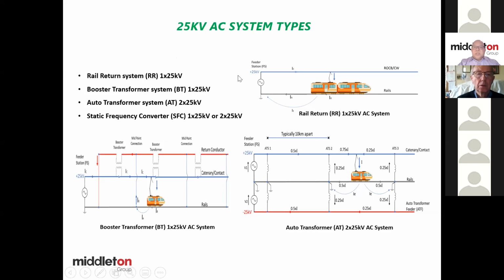The simplest system is a rail return system. Where you have a source, 25 kV AC, feeding a train via the overhead line and returning via the running rails. And of course, there will be some leakage current. I'm going to introduce to you 2 terms for AC railway. I would call this a feeder station rather than substation. And the leakage current, not stray current. We reserve the word DC stray current for DC system. So this is the simplest system you can get. Of course, being simple, that means any leakage current, you have no control where the current is flowing. So it could be in somebody else's water pipe, gas pipe, or whatever, and you have no control.